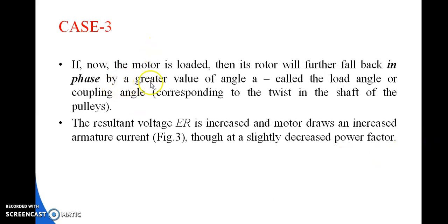Case 3. Now the motor is loaded, we have already discussed that. Then its rotor will further fall back in phase by a greater value of angle alpha, called the load angle, or coupling angle also we can say. The resultant voltage ER is increased and the motor draws an increased armature current, at a slightly decreased power factor we can say.